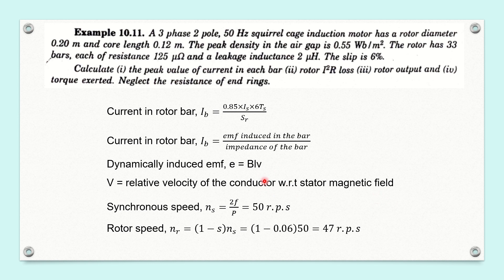The value B is directly given: the maximum flux density is 0.55 Weber per meter square. The length of the rotor bar — the length of the rotor conductor — will be the same as that of the rotor core length, that is 0.12 meter. So B and L are known. Now we need to know the value of V, the relative velocity between the stator magnetic field and the rotor conductor in meter per second.